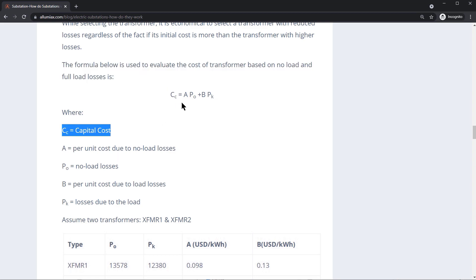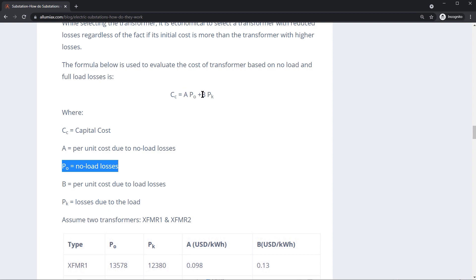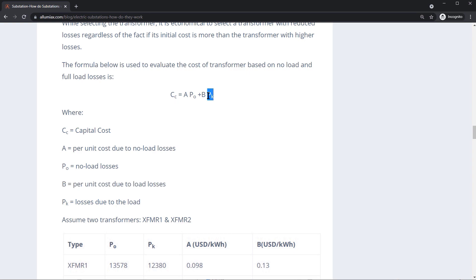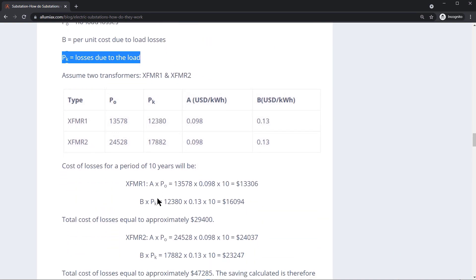The formula used to evaluate the cost of a transformer is based on no-load and full-load losses. The capital cost equals A times P0, plus B — the per-unit cost of load losses — multiplied by PK, which represents the losses due to the load.